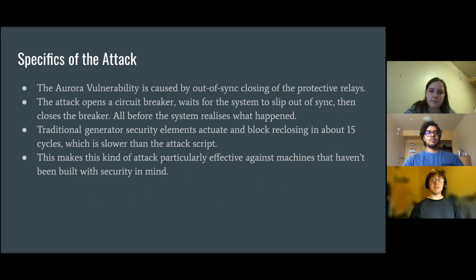The specifics of the attack, as previously mentioned, involve an out-of-sync closing of the protective relay, which is effectively a safeguard component in most generators that ensures they connect to the local network or disconnect when they're in or out of sync, respectively. This attack compromises that protective relay and forces the generator to deliberately speed up or slow down to go out of sync, then reconnect to the grid, cause damage, disconnect, and repeat as many times as necessary to destroy the generator.